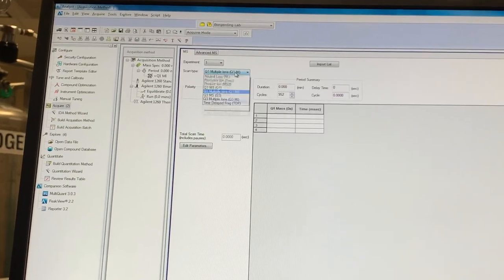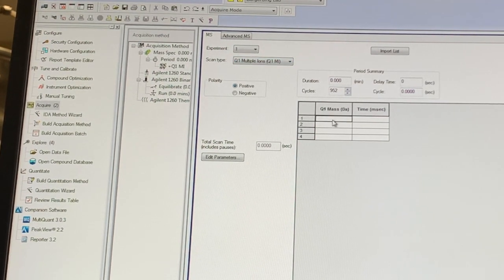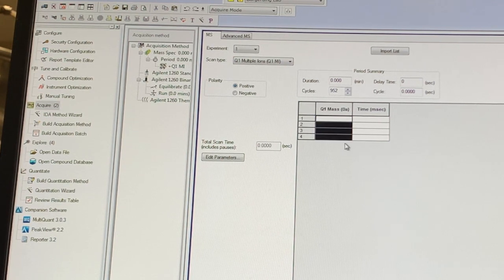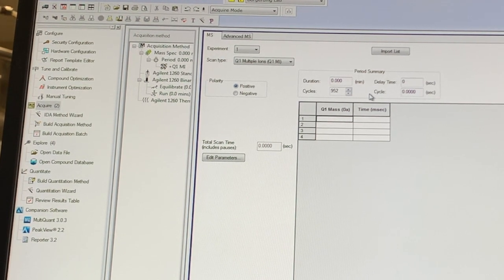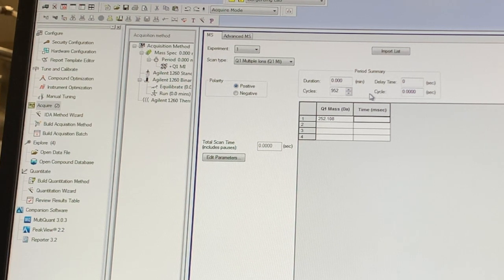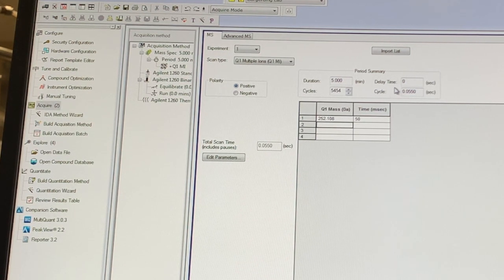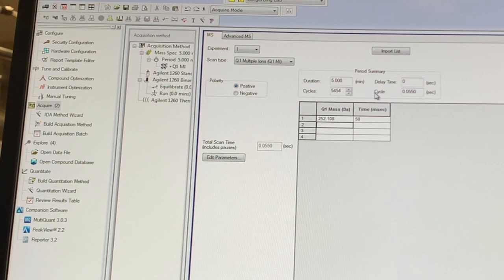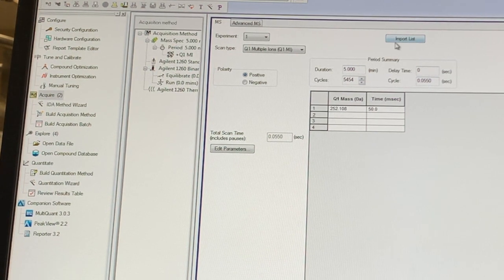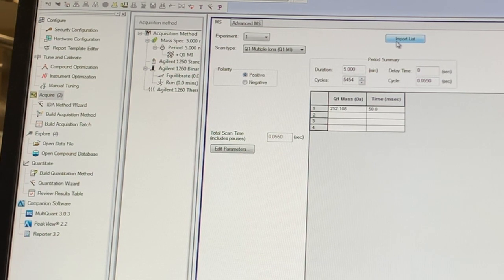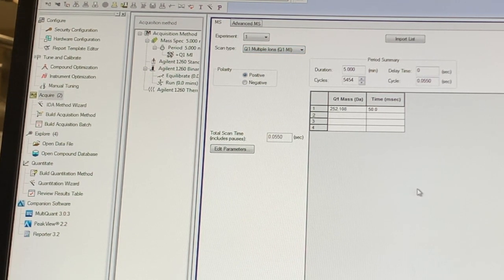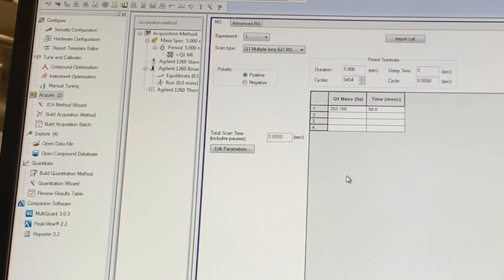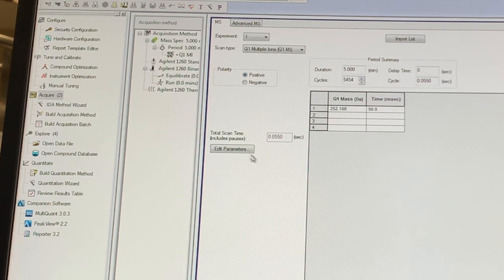This method is called Q1 multiple ions, Q1MI, and it's an example of the selected ion mode methods. So here we can list various masses that we want to detect, and I usually go out to three decimal places and put 252.108. And then we set a time for detection, and again, this depends on the length of your list. If you have more masses on your list, you probably want a shorter time to keep that cycle time up here around one second. Here you can also import a list of masses, which is really helpful because the software actually clears all of your masses if you have to change the scan type. So it's nice to have an imported list of all your masses. Some of my methods that I have have 30 masses that I monitor, so it's very painstaking to have to re-enter all 30 of those. It's nice to have a list on hand.